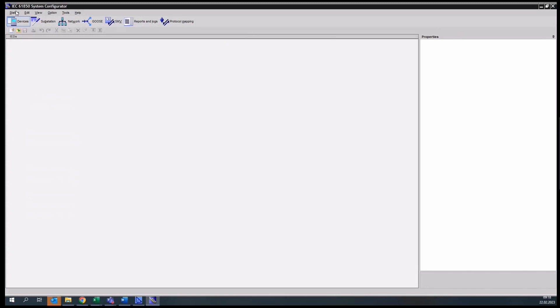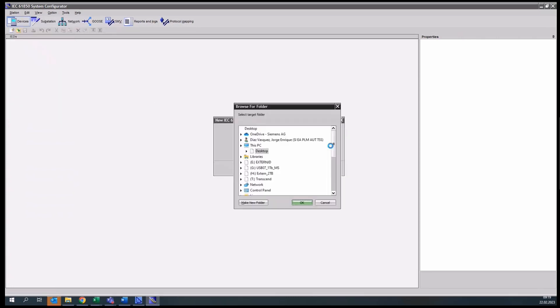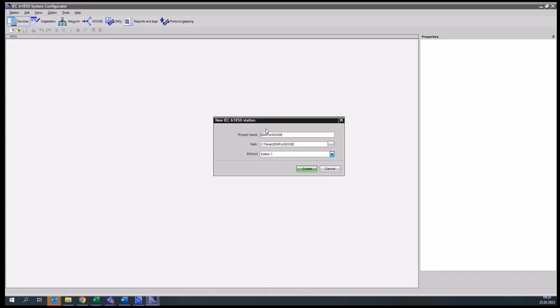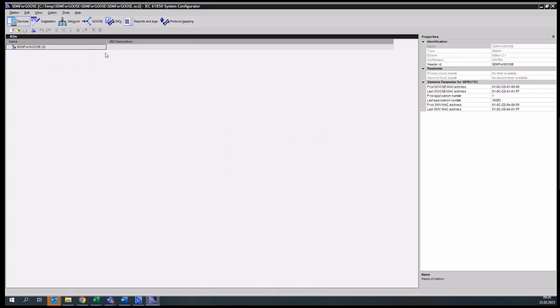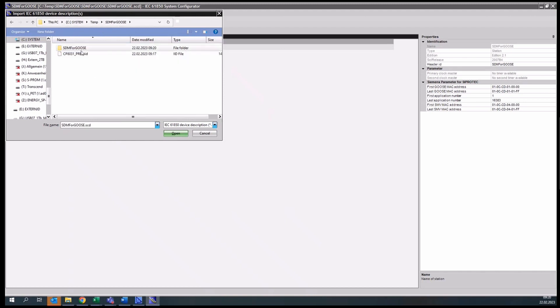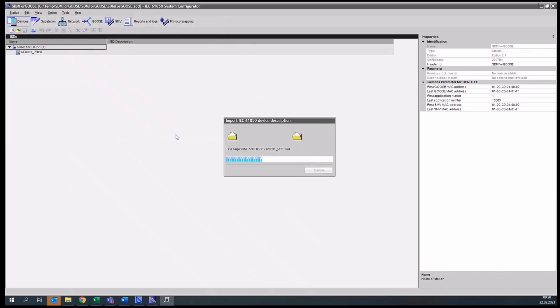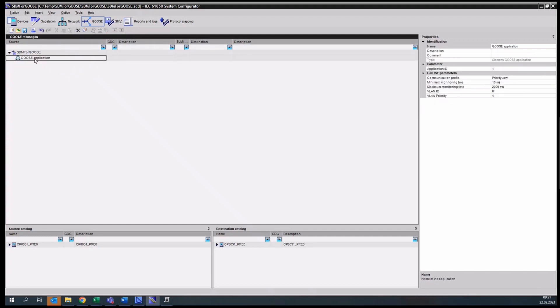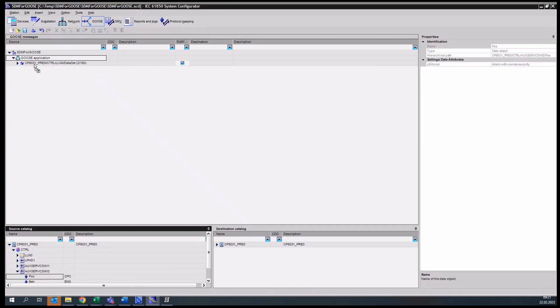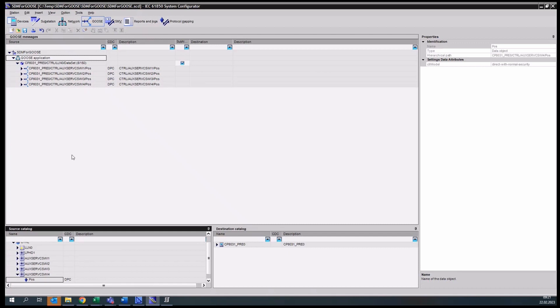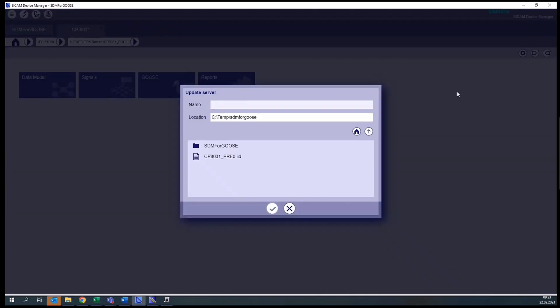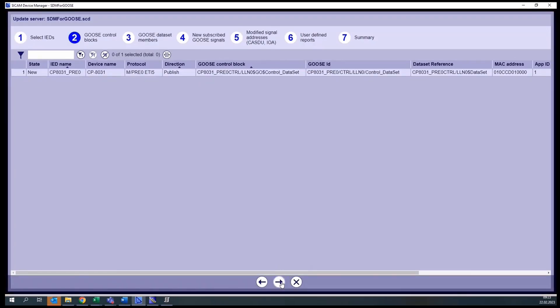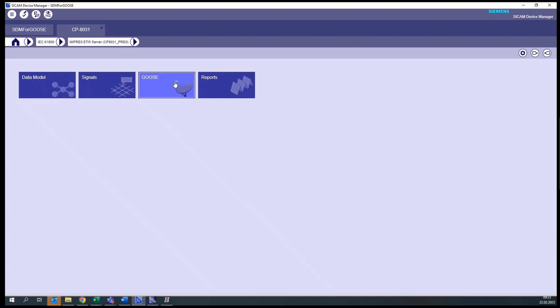First, we will have to create an SCD file to include our IED file. Let's create a new station and select the folder where we will be working. We can call the station SDMF for GOOSE. We choose the same edition that we defined while creating the data model. To include the IED file in this SCD file, we select through right-mouse-click the 'Add IEC 61850 devices' option, and now we select the IED file that we exported. Since we want to publish information via GOOSE, we click on GOOSE, add one GOOSE application, and in this GOOSE application we define which information we want to publish — which signals we want to send via GOOSE. We save it, then go back to SICAM Device Manager, go to IEC 61850 Server, and import back the SCD file. Now we can see that all the required configuration to publish GOOSE messages has been included in the configuration.